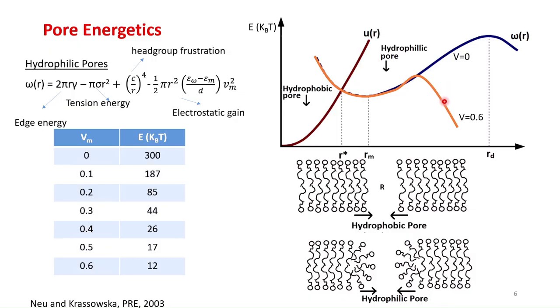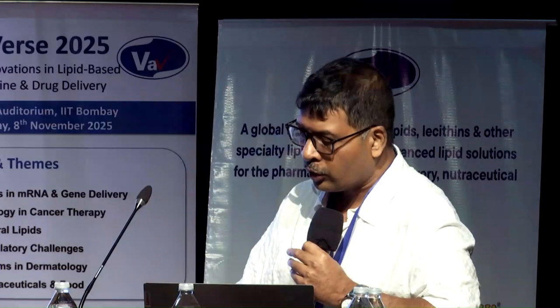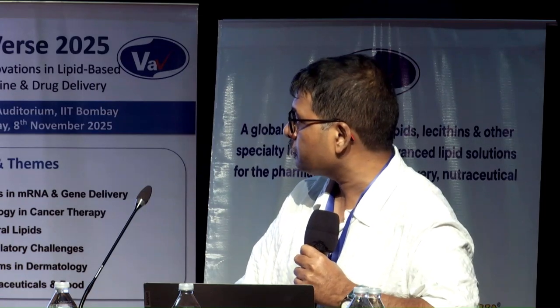And so you would want to switch off the field. And as soon as you switch off the field, it may go here and come back. Okay. So you can have controlled formation of pores just as defined by this equation by suitably adjusting two things, the strength of the electric field and the duration of the pulses. Okay. So that really is the heart of electroporation as a technology.